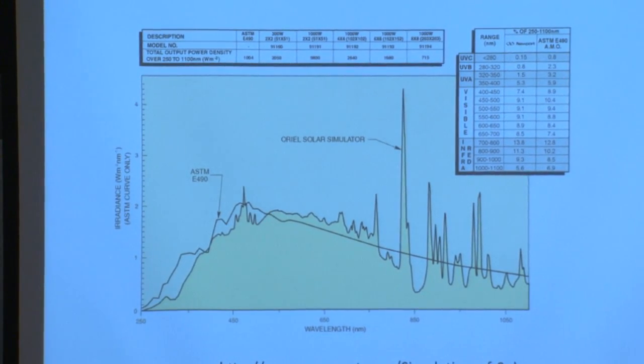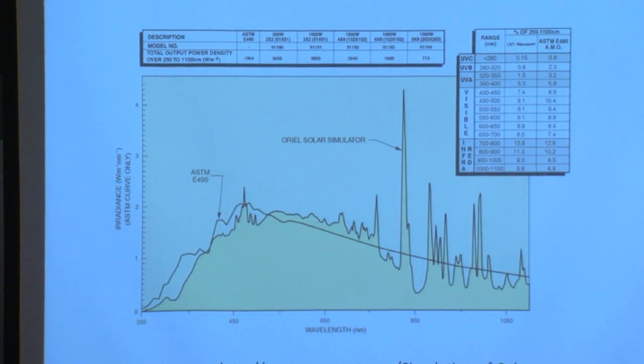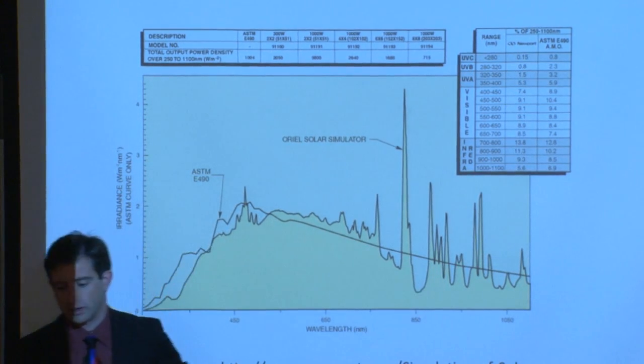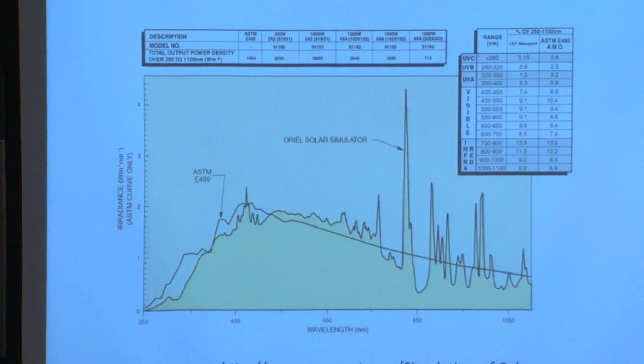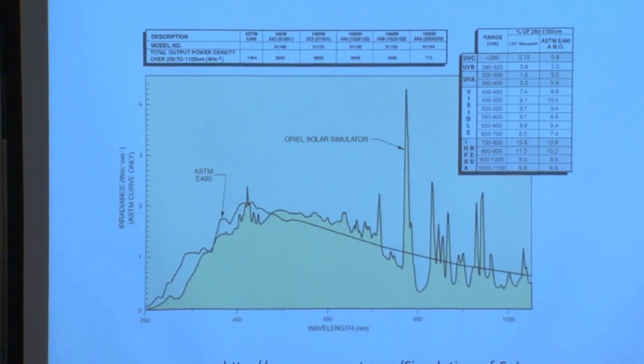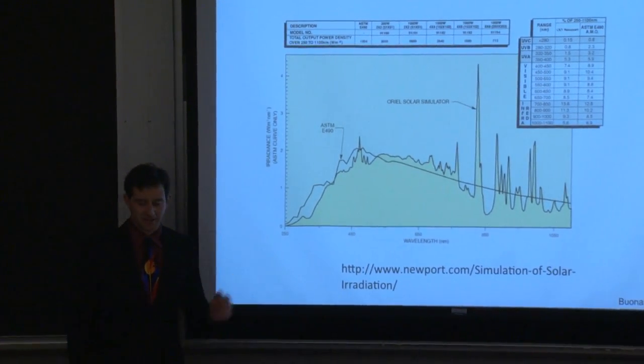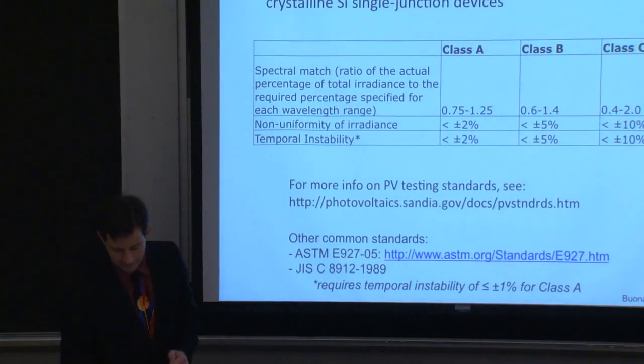This is of some concern if your device is particularly sensitive to a spectral region where those might be present. So it's not a bad idea to take a measurement of your light source and actually understand how it compares, how it matches up against the ASTM standard spectrum.